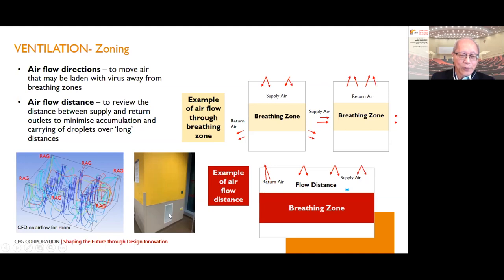This is one of the projects we did where we provide low level return air. Another approach is where air is supplied at ceiling level and returned at one end of the room—some of the air may have to travel a certain distance across the room and deteriorate in quality, picking up more pollutants and viruses. If we provide an additional return air point, the travel distance of the air is reduced, lowering the risk.